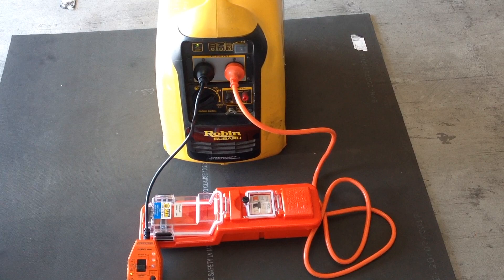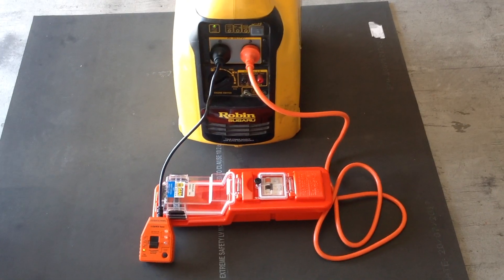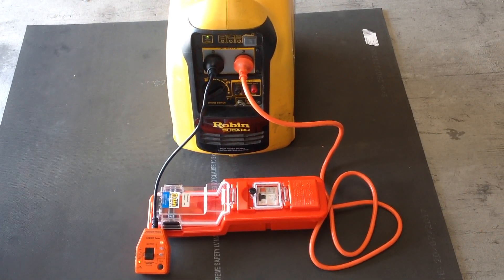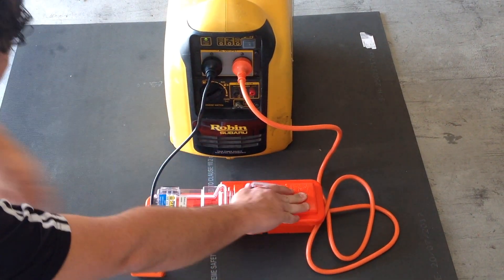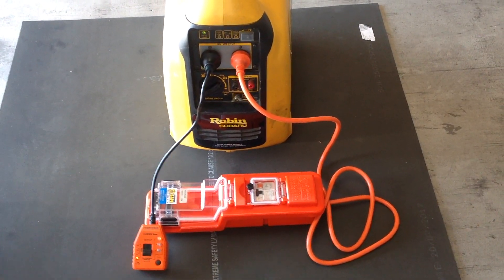In this situation, we have plugged our RCD tester into the generator and are creating the fault upstream of the DUO. This would simulate a fault in the generator, and this shows how the DUO would trip and isolate the circuit that the user has attached their appliances to, alerting them that there is a fault somewhere.